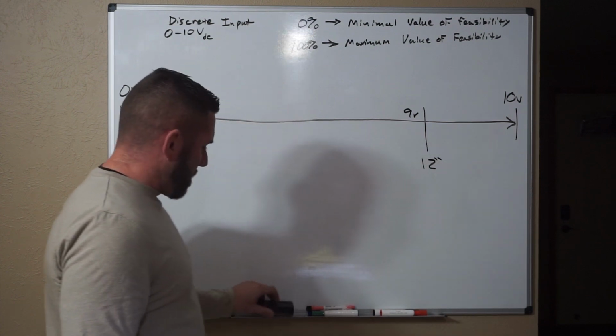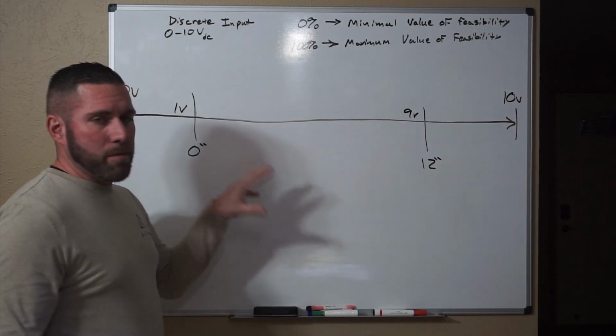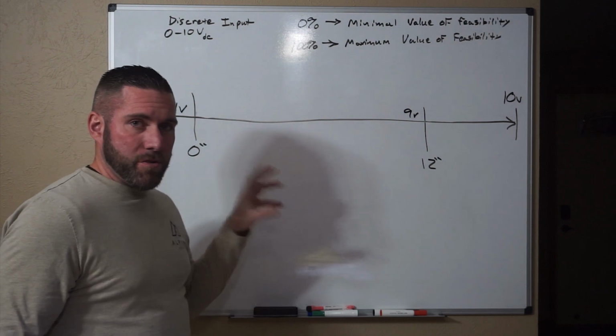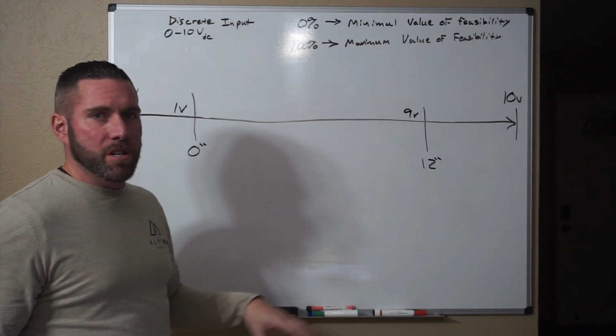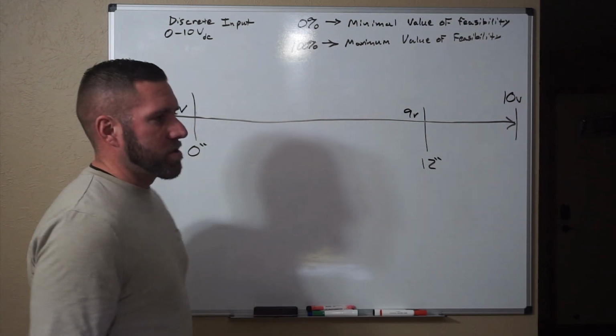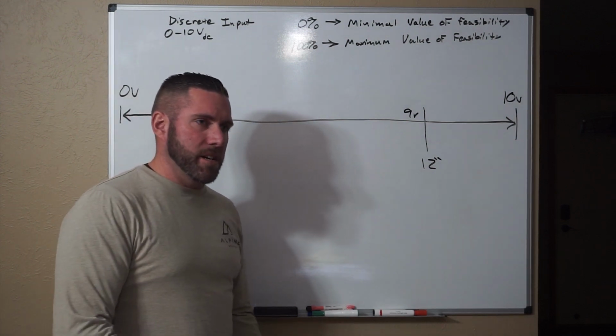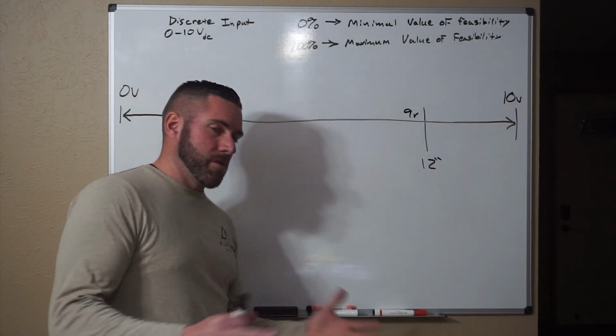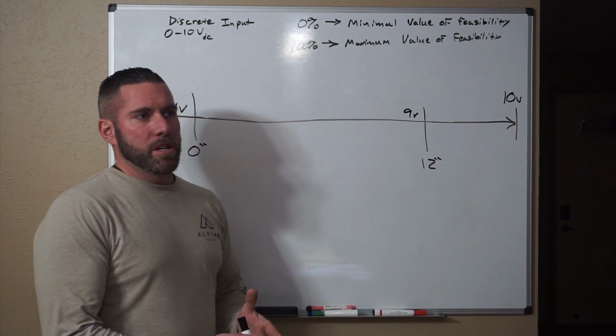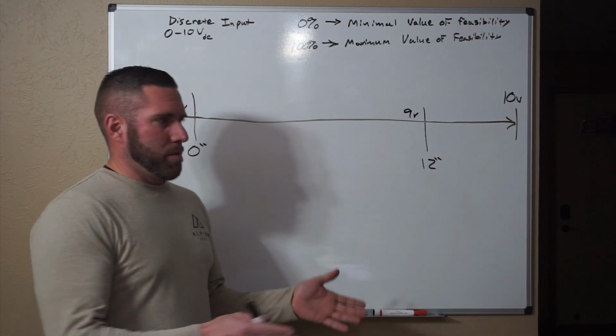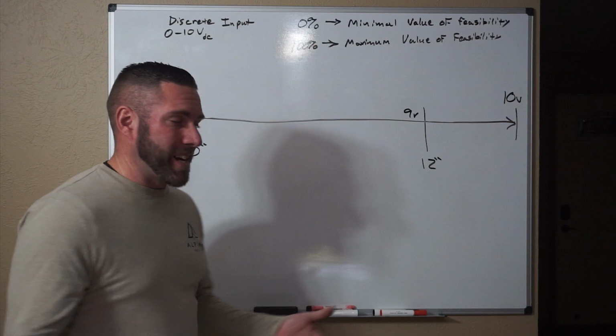Now remember, we sat there and said we need to be able to measure every inch. That is our maximum resolution needed. So how do we pick a sensor for resolution? You're not going to get on a data sheet and have something say, oh, it's 0 to 10, and it's going to measure in volts, about 1 volt per increment. It's not going to happen.